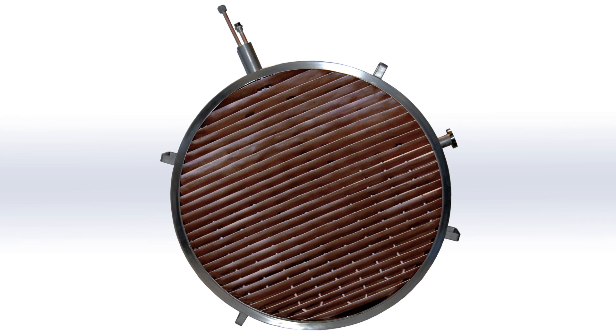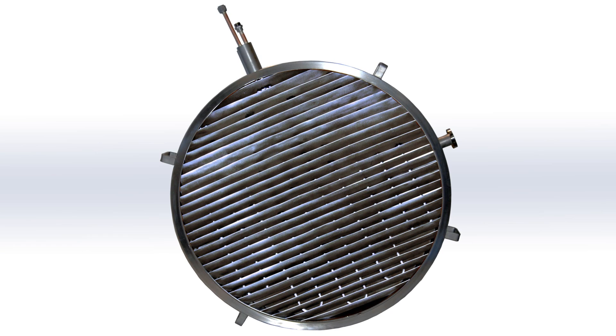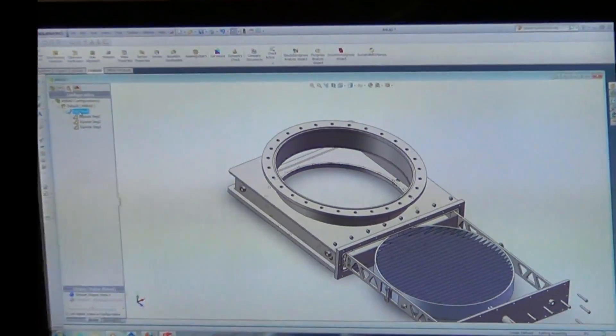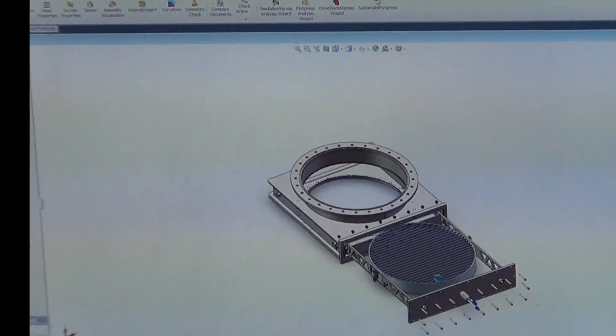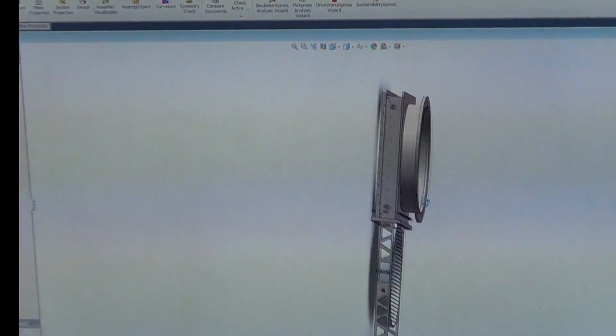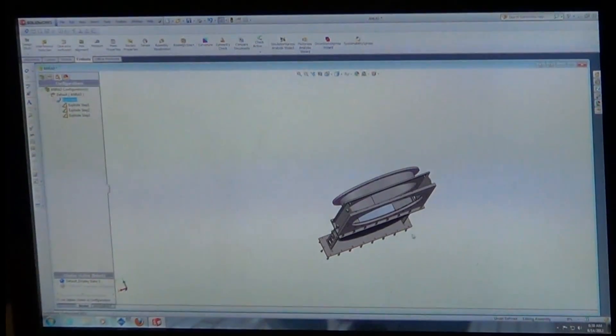For the highest thermal conductivity, choose a chilled surface made from copper; however, for some applications aluminum or stainless steel may be the right choice. For maximum contamination control, GMB manufactures optically dense chevron baffles that require a molecule to touch a cold surface four or five times before passing through. These are capable of capturing more than 99% of the contamination.